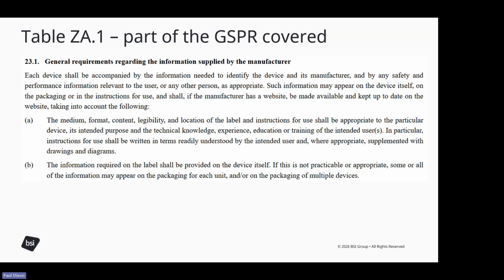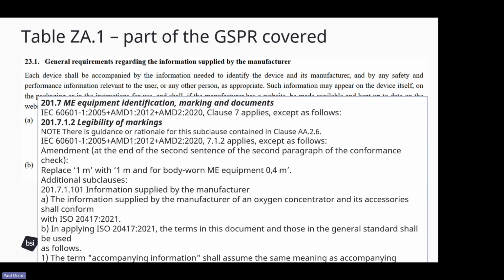Another example, clause 23.1, general requirements regarding information supplied. This is a huge clause within GSPR. It's got bullets that run up to about N. And in this case, we have a clause within the oxygen concentrator standard that talks about legibility of markings and so on, and it also covers information supplied by the manufacturer, and it has a requirement that that information conform with ISO 20417. And it has some additional guidance as to how to apply 20417.